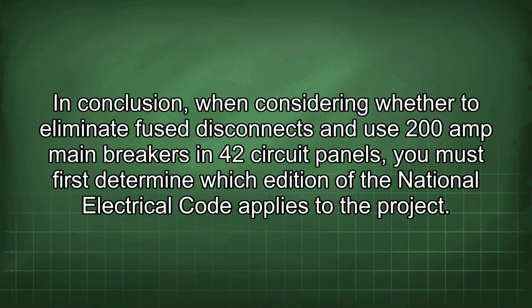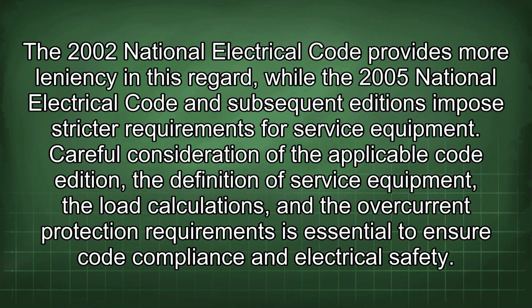In conclusion, when considering whether to eliminate fused disconnects and use 200 amp main breakers in 42 circuit panels, you must first determine which edition of the National Electrical Code applies to the project. The 2002 National Electrical Code provides more leniency in this regard, while the 2005 National Electrical Code and subsequent editions impose stricter requirements for service equipment. Careful consideration of the applicable code edition, the definition of service equipment, the load calculations, and the overcurrent protection requirements is essential to ensure code compliance and electrical safety.